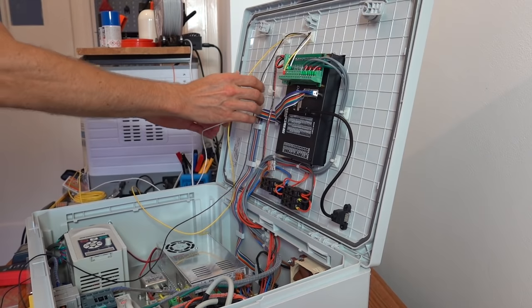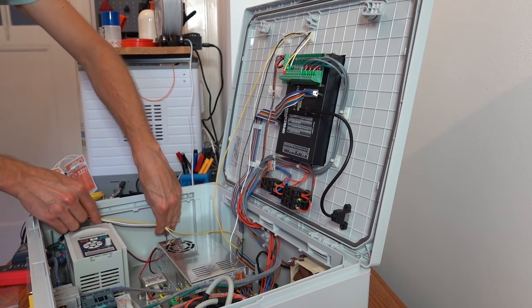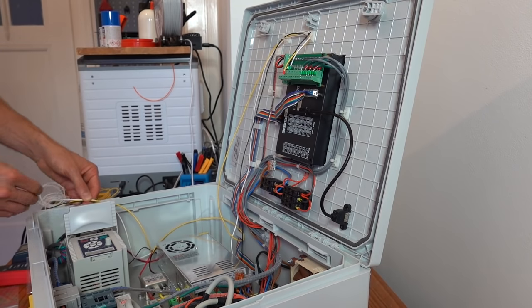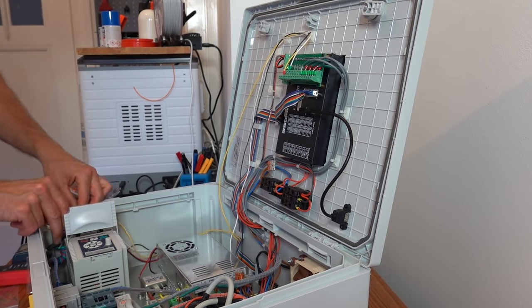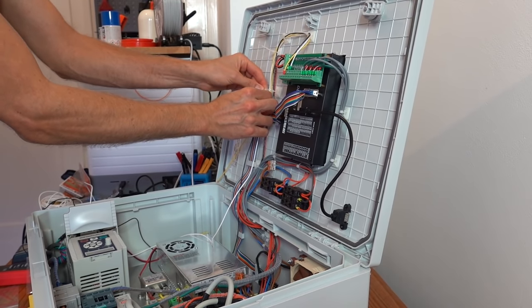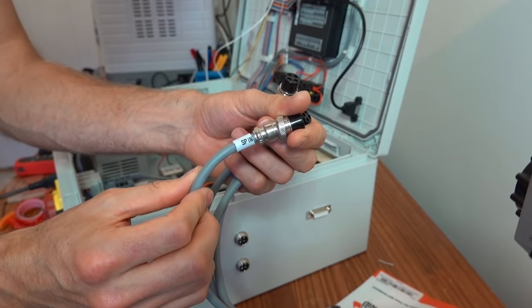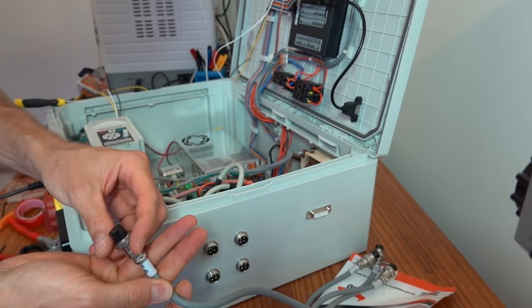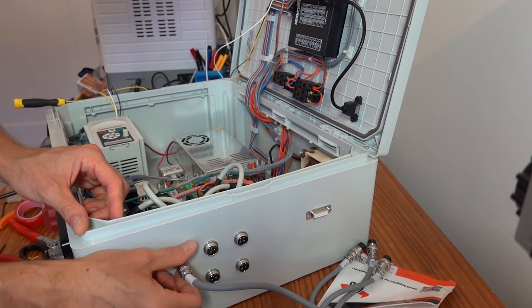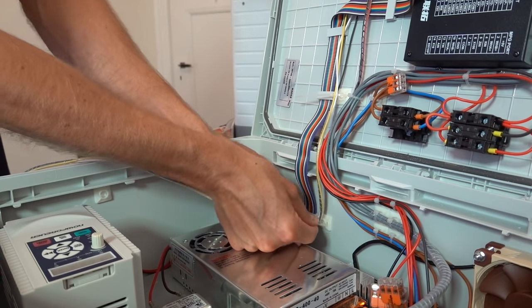In the old situation, my VFD was controlled. I will be controlling the VFD in the same way, using the 0 to 10 volt signal input to control spindle speed. On both the DDCS controller and the VFD, I am indicating that at 0 volts the spindle should stop and at 10 volts the spindle should be at maximum RPM. In this case, 24,000. Any other voltage in between will set the spindle to the corresponding spindle speed. For example, if your NC program has a spindle speed command for 12,000 RPM, the DDCS controller will output 5 volts and the VFD will then know it has to control the speed to 12,000 RPM.